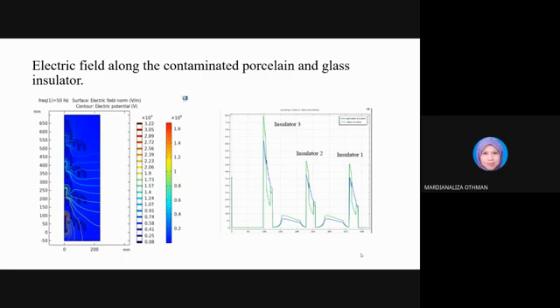For each insulator in the insulator string, it can be found that the electric field strength exists at the bottom pin and the point where the ceramic and cement meet inside the cap of the insulator. The electric field is greatest near the pin of insulator 3 and decreases gradually when moving outward. The highest electric field is the contaminated glass, with 800 kilovolt per meter.